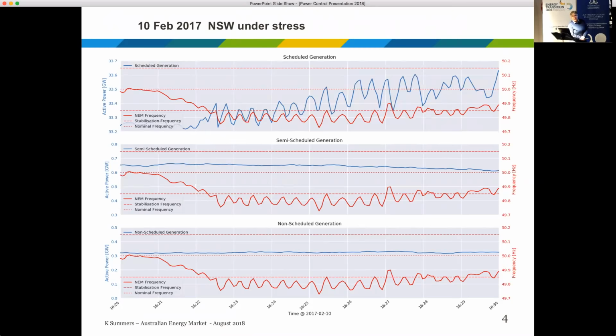Then the active power on the large scheduled generators, the top plot, is oscillating with a 24-second oscillation for 7.5 minutes before they figure out how to get the frequency back into the normal operating band. Now the scheduled generators are the synchronous generators.